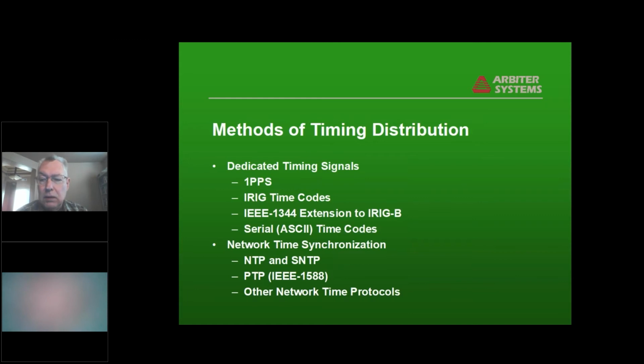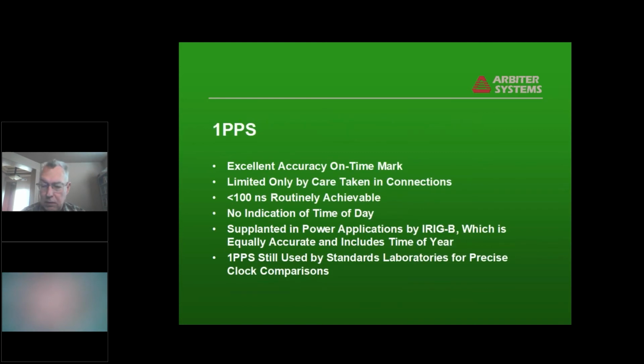Okay, now we've got this accurate time signal. How do we get it out into the IEDs that need it? There are a number of different ways of doing this, and I'll talk about each one of them, including 1 PPS, 1 pulse per second, which is basically an electrical signal, and IRIG time codes. The Inter-Range Instrumentation Group, a military group, originally developed that. There's an IEEE extension to that, and we have serial time codes that can be sent over an ASCII link, usually used to synchronize computers and displays and other things that don't require super high accuracy. And then we've got network time synchronization, NTP, SNTP, you've heard of, I'm sure, and PTP or IEEE 1588, and there are some other network time protocols as well.